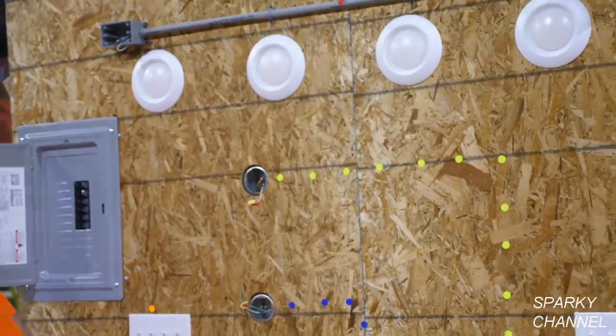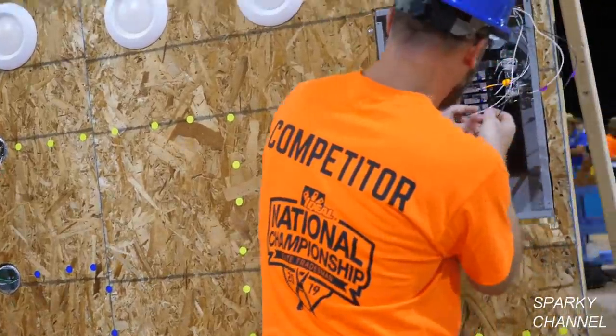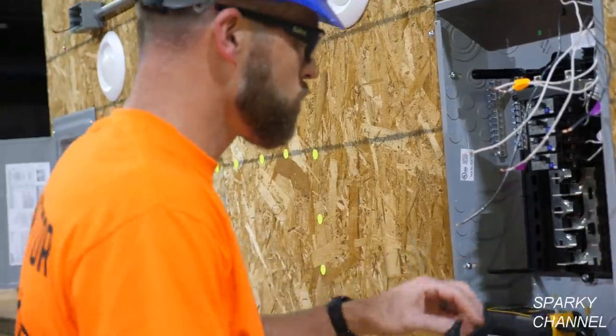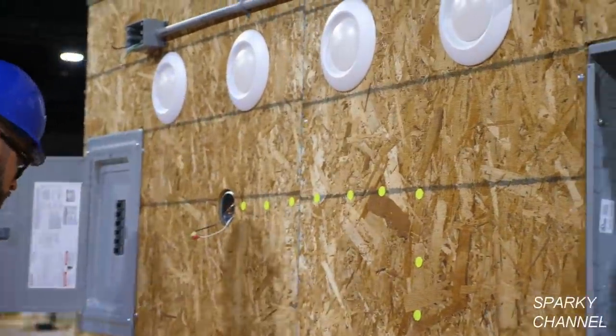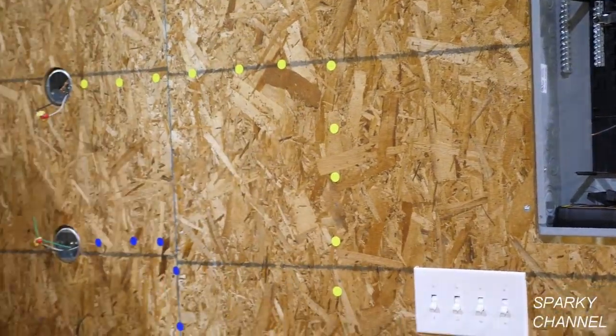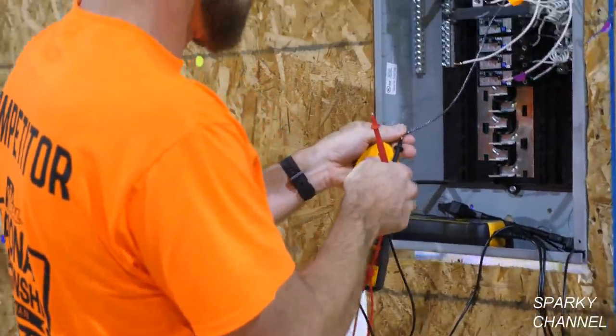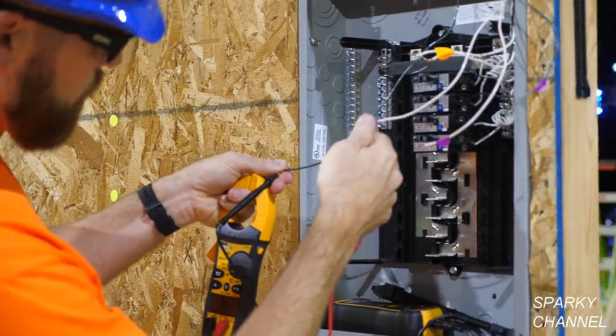In the de-energized panel, the circuit breaker for circuit number 8 will not close due to a lighting fault. Greg is to use the TightSite meter and the SureTrace circuit tracer to identify the conductors involved and precisely locate the LED lighting outlet fault. He's to use green stickers to put a flag on each of the faulted conductors and also place a green sticker on the LED lighting outlet to identify the precise location of the fault. That fault affects circuit number 8.